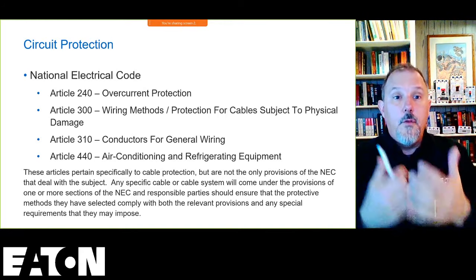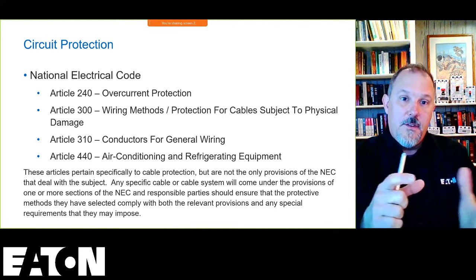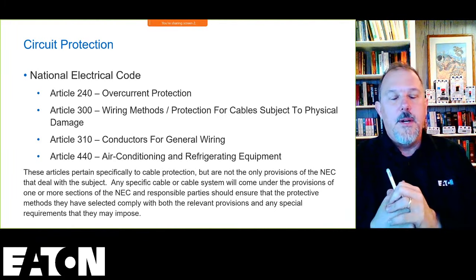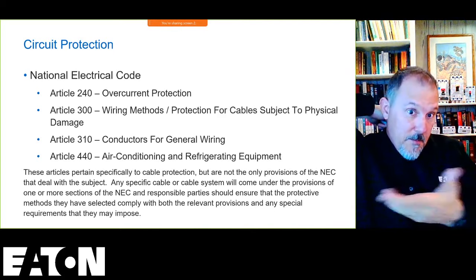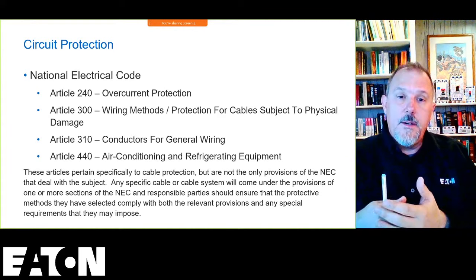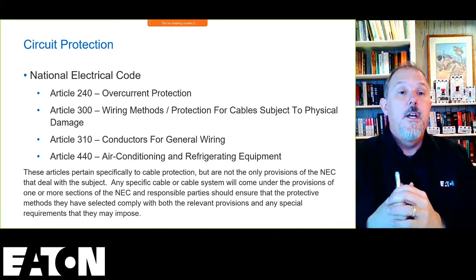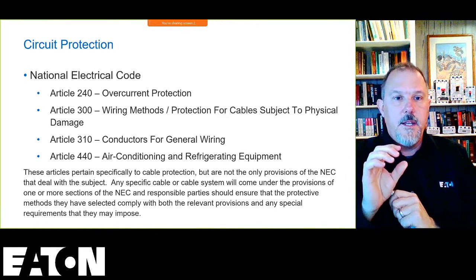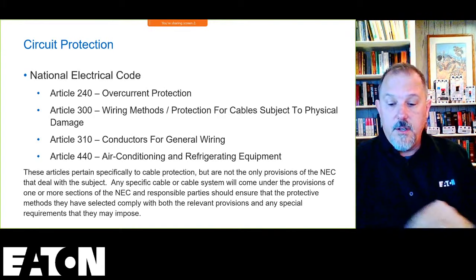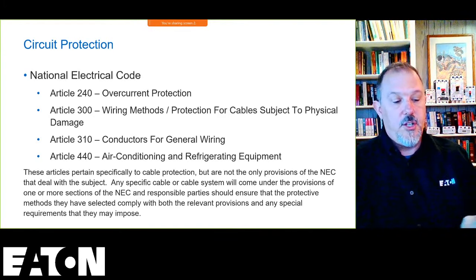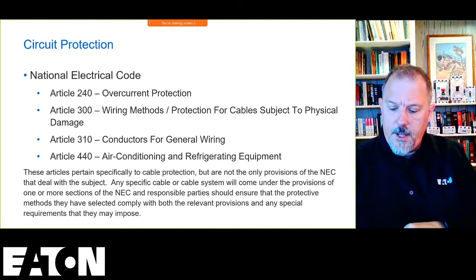So you have Article 240, 300, 310, and I threw 440 in there. I've had these sets of slides for quite some time. I added 440 because of the problem that we were reviewing, which is an air conditioning and refrigeration unit, three air conditioning units up on the roof. So Article 440 is important for determining the overcurrent protection of those branch circuits, from an overcurrent and short circuit protection standpoint.